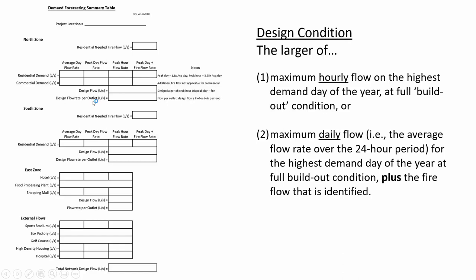The design flow rate per outlet is the design flow divided by two, because there are two interior locations where water is being delivered inside the north zone. Same thing with the south zone — there are two arrows pointing into the south zone on the map. The residential demand, the bigger of peak hour or peak day plus fire, is the design flow, and the design flow per outlet is that divided by two.